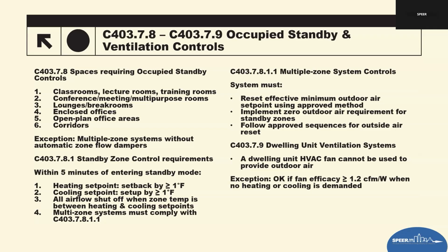The 403.7.8.1, what happens during standby mode? When the space transitions to standby mode, usually based on time of day or occupant sensors, the HVAC system must adjust within 5 minutes. That's a common theme in the 2024 code, as they've added these 5-minute allowances.